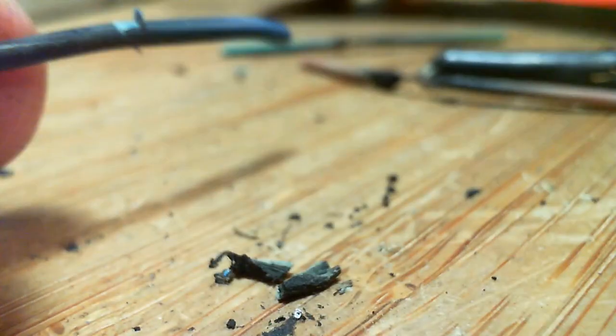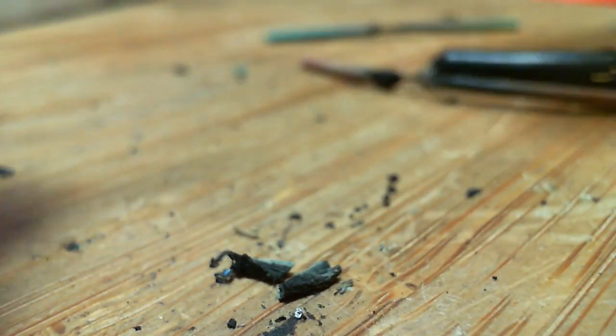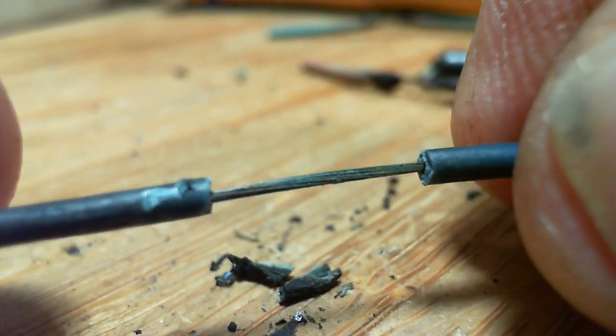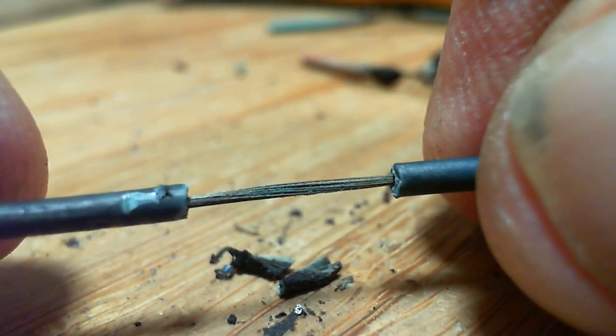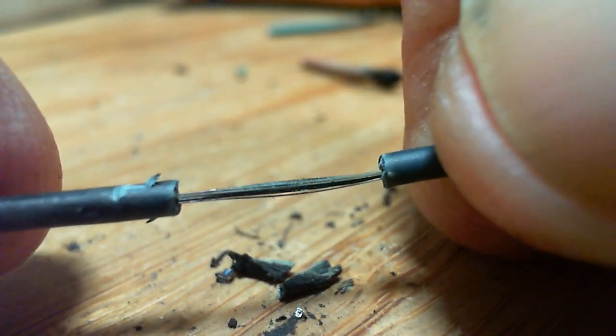So I used to keep records on all the cable failures. A one pager, a little report I made up. Photographs, diagrams, any information I picked up about it that was of any significance. So you can think of these cables as being a kilometer or two long, and when they fail, look at how there's corrosion in this.